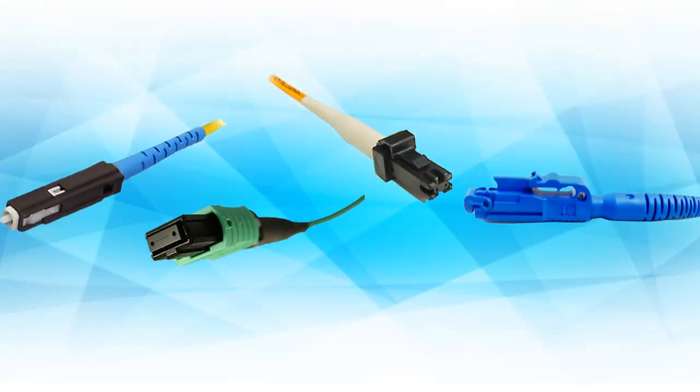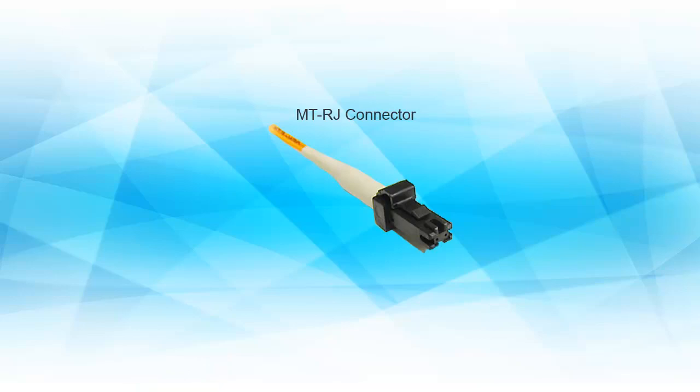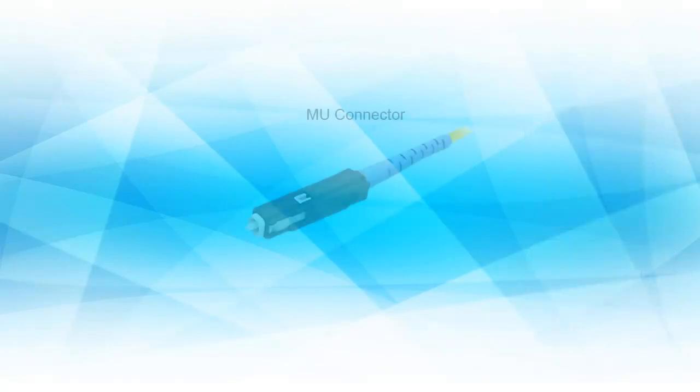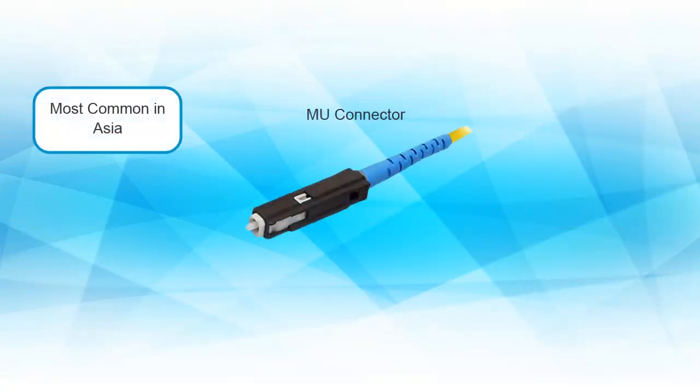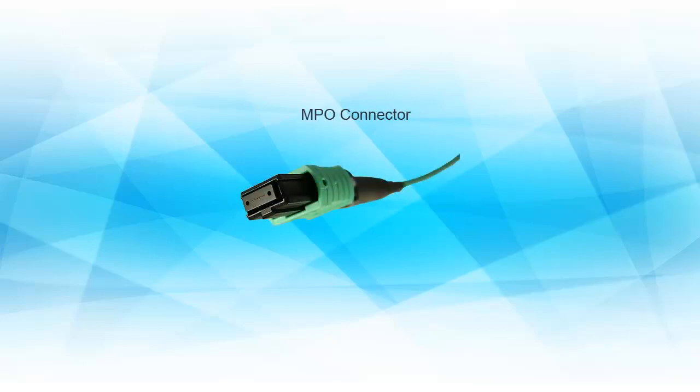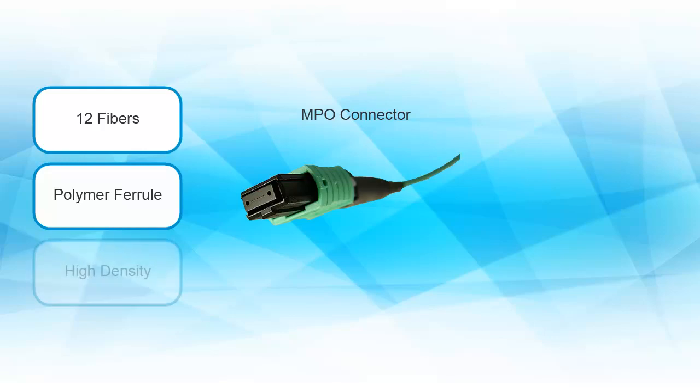You may still see other types. The MT-RJ, a duplex connector with both fibers in a polymer ferrule and pins for alignment. It has an existing base, but few new installations. The MU looks like a miniature SC with a ferrule the same size as an LC, but this connector is most commonly used in Asia. The LX-5 is like an LC connector, but with a shutter. The MPO connector is a small connector about 10 millimeters wide containing 12 fibers in a polymer ferrule and these are commonly used in data centers where high density is required.